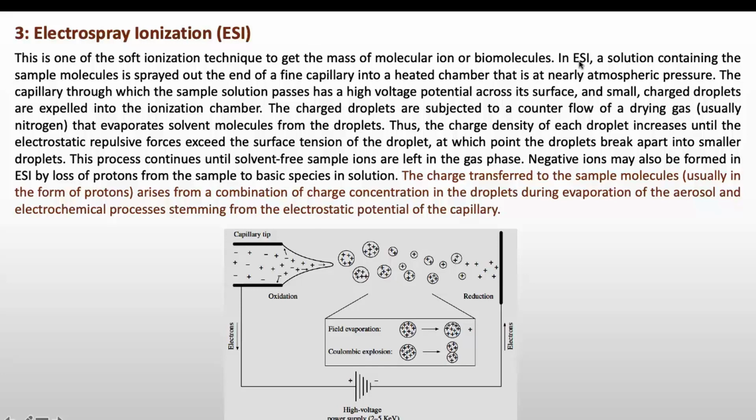So in the ESI or electrospray ionization method, a solution containing the sample molecule is sprayed out of a fine capillary into a heated chamber that is at nearly atmospheric pressure. The capillary through which the sample solution passes has a high potential across its surface, and small charged droplets are expelled into the ionization chamber like this. The charged particles are subjected to a counter flow of a drying gas.